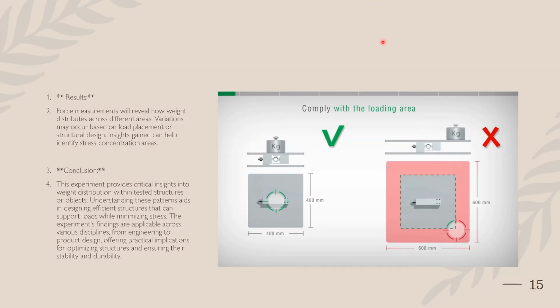So I have an image here to explain what exactly happens when we place weight at the center or not near the center. When we are placing the weight near the center, we can see that the mass is correctly aligned with the experimental setup, and in this case we get an accurate reading. But when we place our mass not in accord with the alignment of the setup, we will get a misalignment, and this misalignment will lead to error. And as we have seen earlier, the error can go up to 70%.